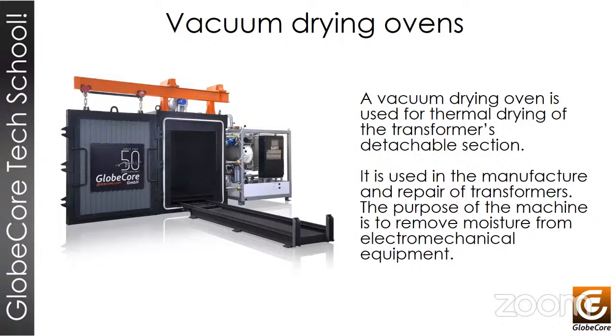The purpose of this machine is to remove moisture from electromechanical equipment. This equipment is used at transformer manufacture and repair facilities. In the process of manufacturing, the main function is drying or preparation of a winding, maximizing the insulation characteristics prior to installation in the transformer and filling it with oil.